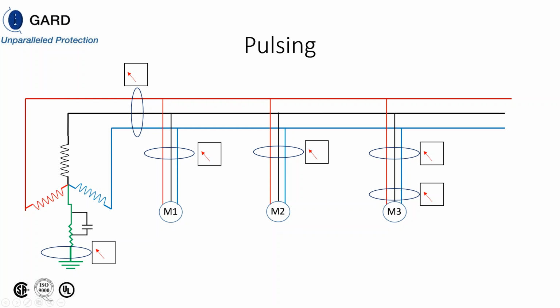All right, so this pulsing contactor right here changes the value of the resistor. So remember, we limit the fault current to 5 amps. So we can change that fault current by changing the value of the resistor. On a 480 volt system, 5 amp pulsing, you're going to have a 55 ohm resistor. So let's assume we're going to change the value of that resistor from 55 ohms to 27 ohms. When we do that, we change the fault current from 5 amps to 10 amps.